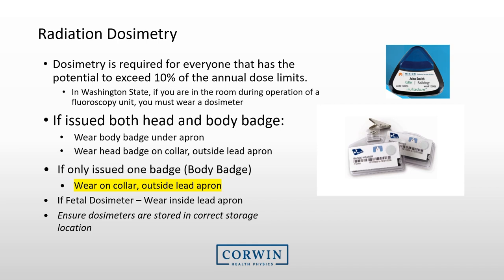Radiation dosimeters, also called film badges or TLDs, are objects worn on your person that measure radiation dose and are exchanged at a certain frequency or read electronically to ensure we know what radiation dose your body is receiving. Radiation dosimetry is required for everyone with a potential to exceed 10% of the annual dose limits. However, in Washington State, if you are in the room during the operation of a fluoroscopy unit, you are still required to have a radiation dosimeter even if you don't have the potential to exceed the annual dose limits.